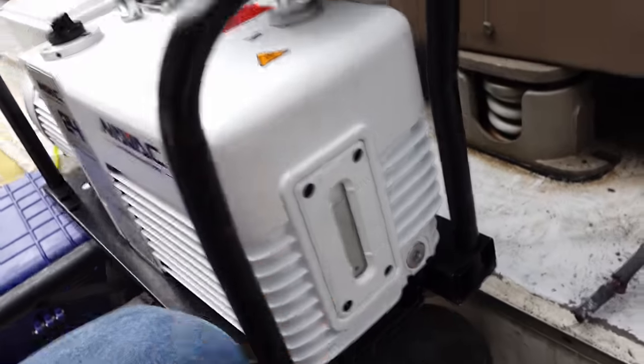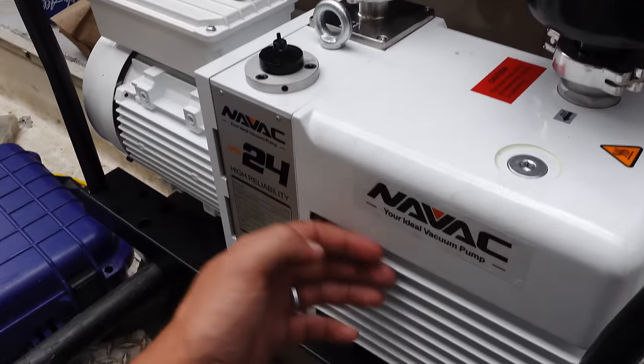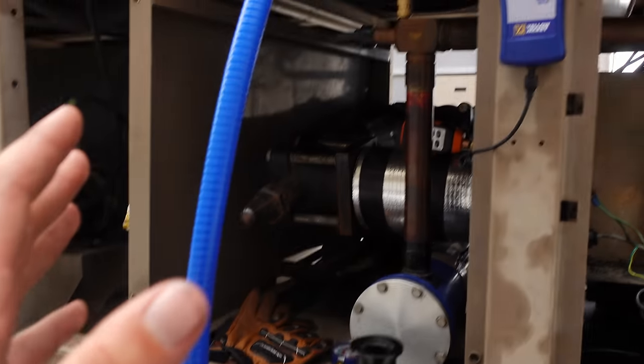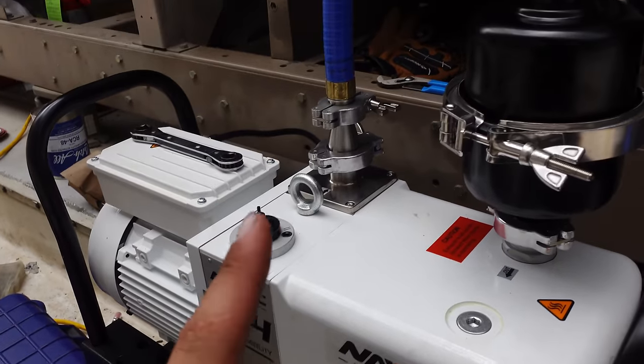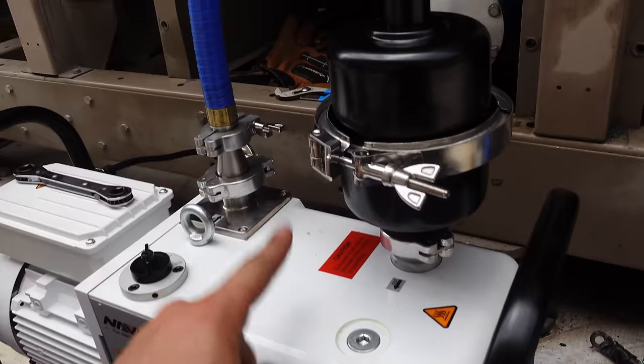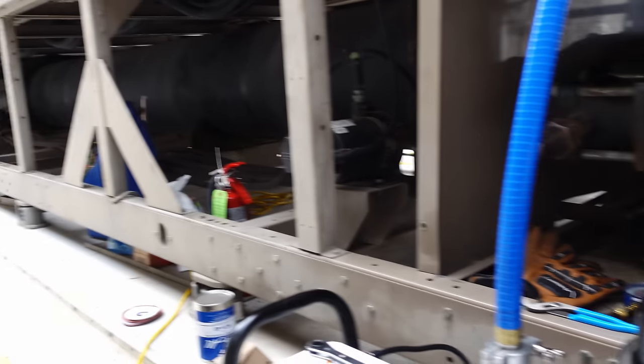My oil has done really well throughout this pull-down. It definitely gets hot — they even have a temperature sticker; they expect it to get hot. It has done a fairly decent job regulating temperature, which a lot of pumps don't do and that's part of their downfall. Good on NAVAC for that so far. My four-hour window that I was hopeful for — I wanted to see what it would do — I don't think it's this pump's fault that we didn't achieve that. I think it has more to do with just the overall conditions surrounding the job.